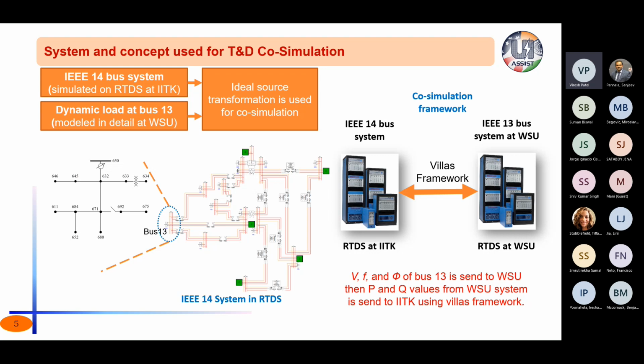So in ideal source transformation co-simulation, suppose we want to simulate the load at bus 13. The bus 13 voltage, frequency and phase is sent to the other location, where the other simulation is running, like the IEEE 13 bus system simulated at WSU. So their voltage, frequency and phase is sent, and then the simulation is run. Then the P and Q from the IEEE 13 bus is sent back to bus number 13 through a Villas Framework. And in this way, the co-simulation is executed.